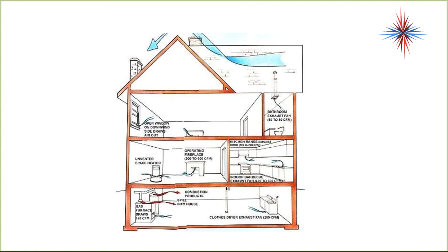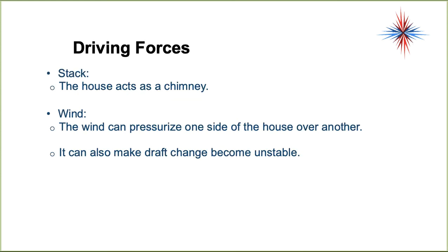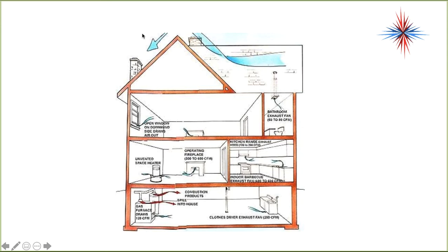Now let's talk about pressure across houses. There are several driving pressures across houses. The stack effect — the house acts as a chimney: hot air rises, cold air falls. Wind can pressurize one side of a house over another and make draft change become unstable. Wind blowing across a roof can blow down a chimney and cause furnaces to vent in reverse. On the windward side of a house, wind pushes into openings; on the leeward side, it actually creates negative pressure. Wind on the outside of a building can cause real issues inside.